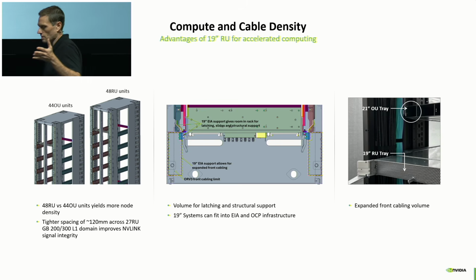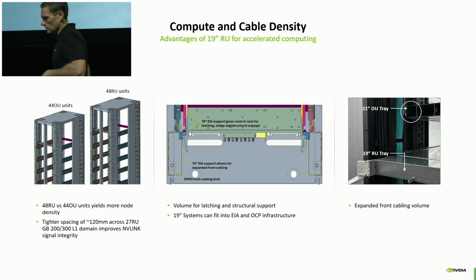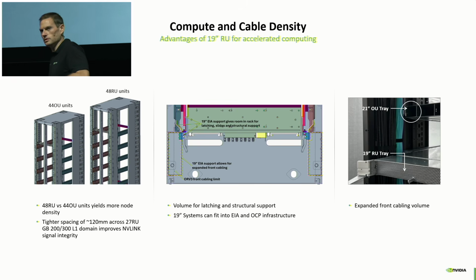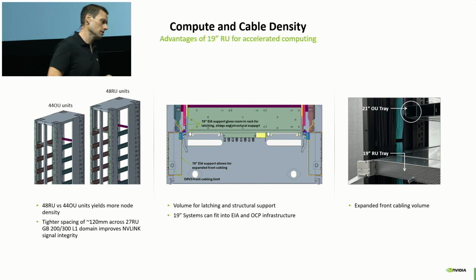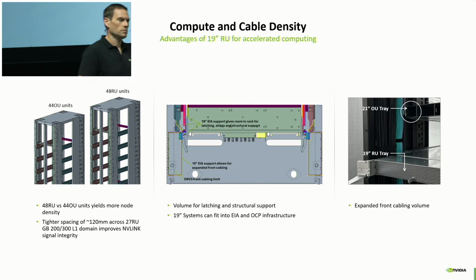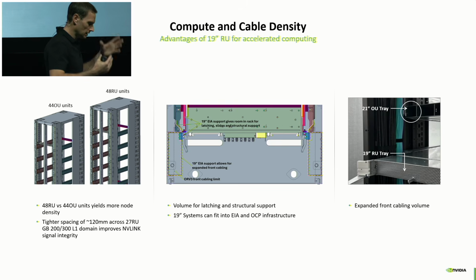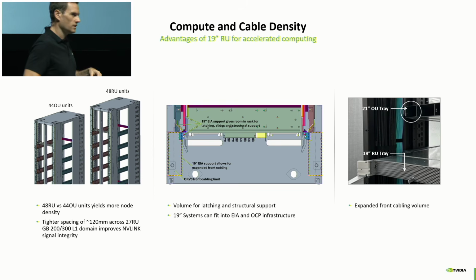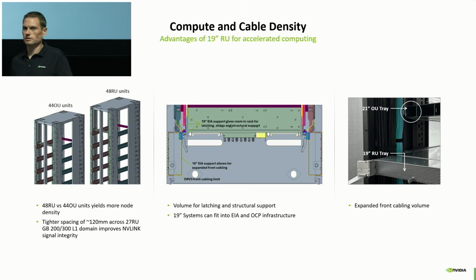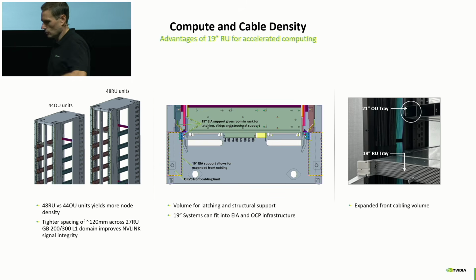NVLink, as I mentioned, runs at 200 gigs per lane. That's not an easy signaling speed to design around. By tightening the pitch and pushing things together, we eliminated 120 millimeters out of the cable length. Doesn't sound like a lot - about 4 or 5 inches - but that has a very positive, meaningful impact on signal integrity through those cables. Every cable has a certain amount of dB per inch, so cutting 5 inches out does you a favor. That was one benefit of the RU pitch.